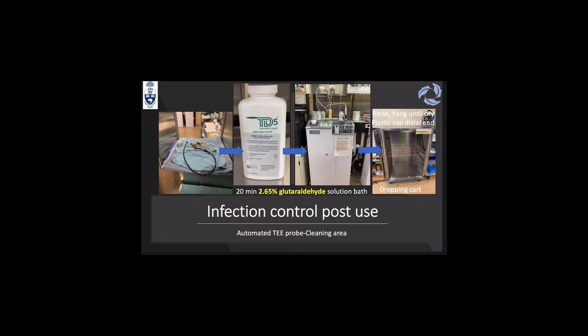Once mechanical cleaning is done, the probe is placed in an automated TEE probe cleaning machine using a 2.65% glutaraldehyde solution bath. The recommendation is to soak the probe for 20 minutes, then let it dry, put a plastic cap on the distal end, and place it in storage ready for reuse. It is recommended to use an air tank to dry the electrical connector and the knob handle to ensure no residual glutaraldehyde remains after the automatic cleaning.